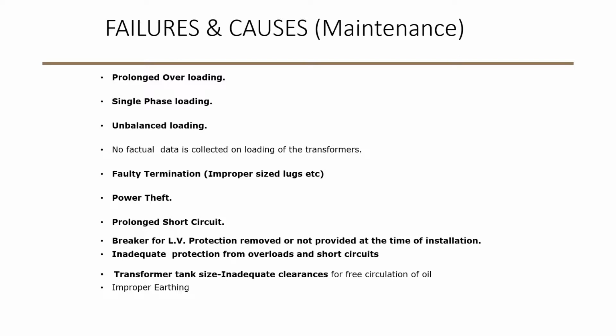Actual data for transformer loading is often unavailable, so we don't know the load profile. Faulty terminations and improper size of lugs cause overheating, and additional tension on terminations also causes overheating. Power theft is another problem we face, along with prolonged short circuits, since distribution protection is not very good—so having an individual protection plan for each transformer is beneficial.